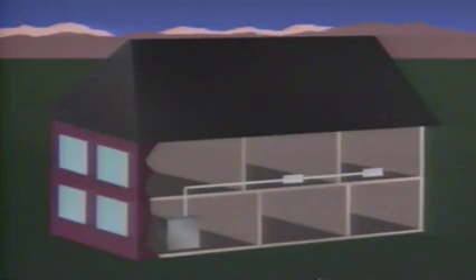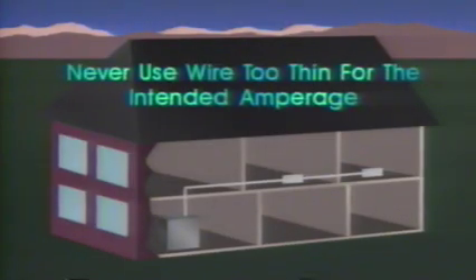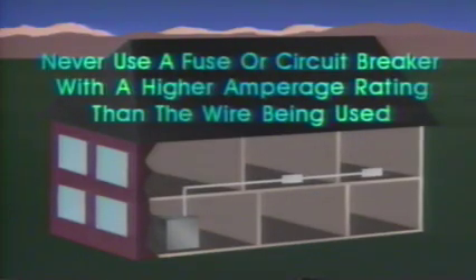If you have questions about what gauge size wire to use for a particular job, check with your local code official. Always remember, any gauge wire too thin for its intended amperage is a fire hazard. Also, never use a fuse or breaker of a higher amp rating than that of the gauge of the wire in that circuit.